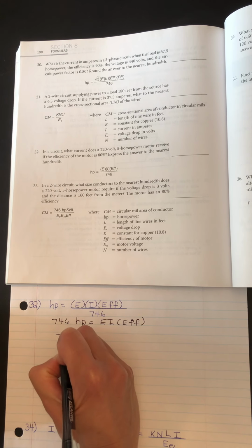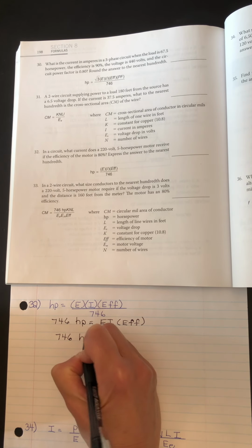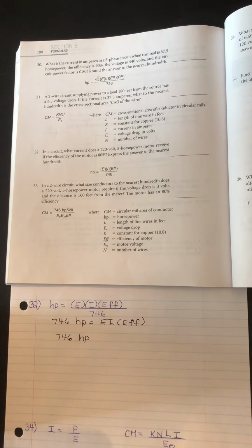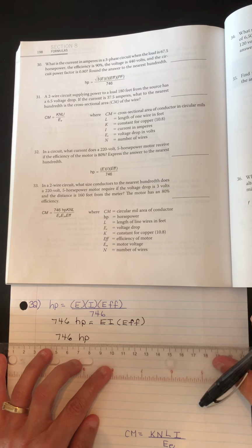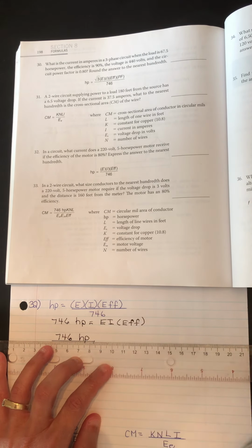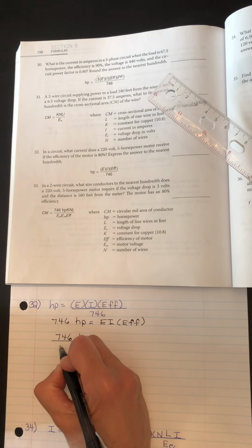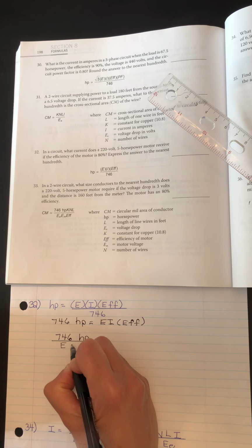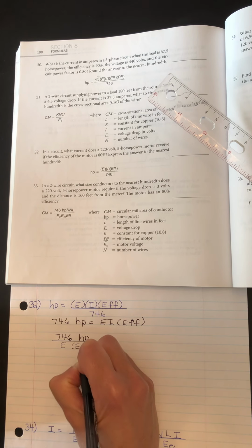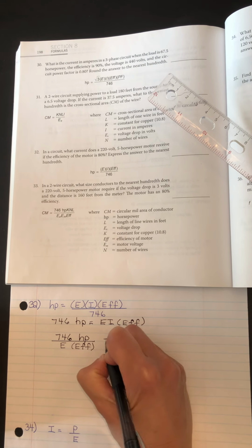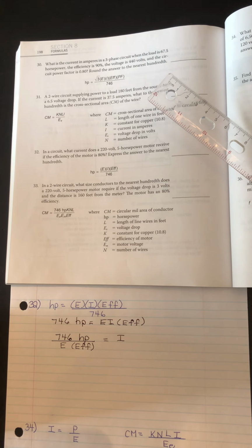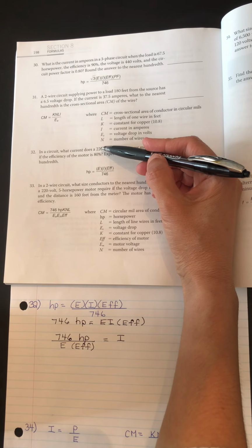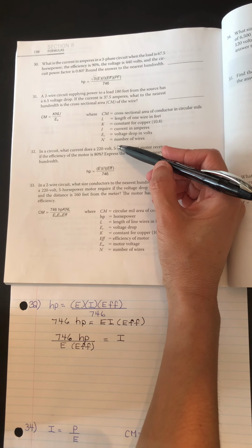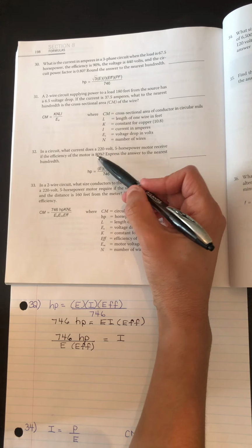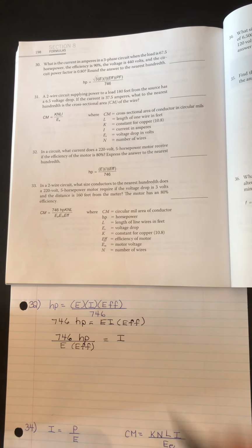So we end up with 746 multiplied by the number of horsepower, and then we will divide by both E and by the efficiency in order to get the current. That's all there is to it. So now we can go ahead and substitute. We're substituting 220 for E, 5 for HP, and 0.8 for the efficiency.